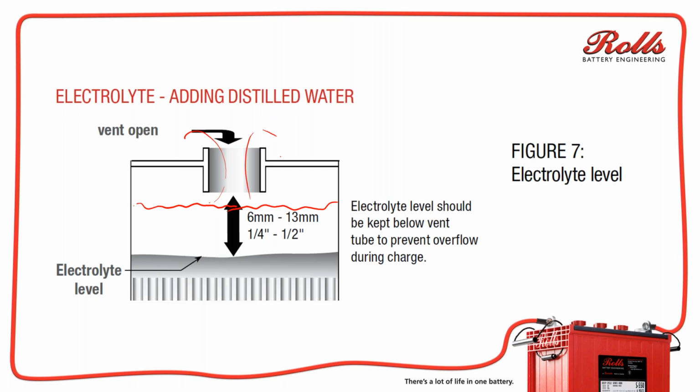So when I get a customer who sends me a specific gravity report, and they're all 1.220, 1.225, 1.230, 1.250, if they're all low, but they're all about the same, and he equalizes those batteries, and those specific gravities don't rise at all, that tells me that client's been overfilling their battery. That tells me the electrolyte's been pushed out, or the sulfate's been pushed out, and you've lost battery capacity because you no longer have the sulfate to make the capacity. That's a definite problem that a lot of people run into: they overfill their batteries quite often. So hopefully that answered your question there, Julian.